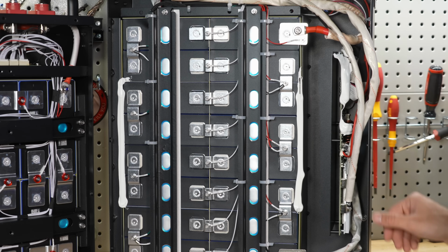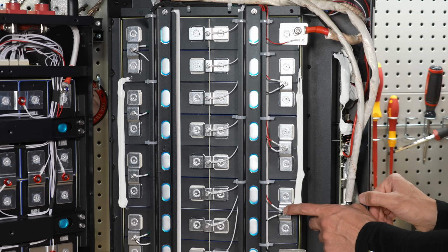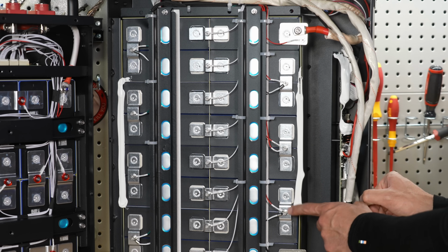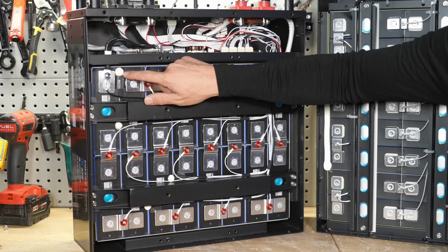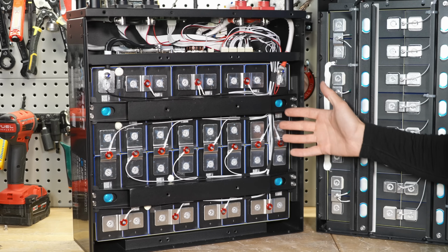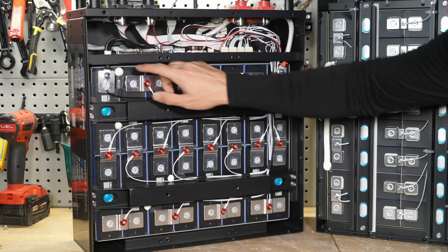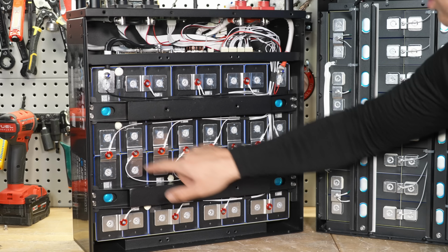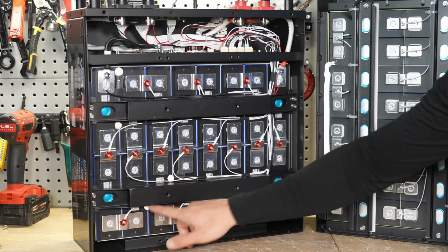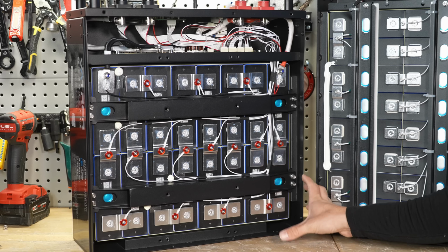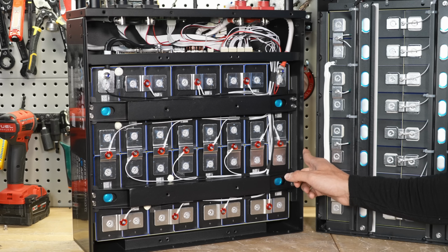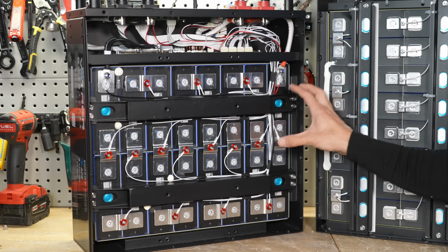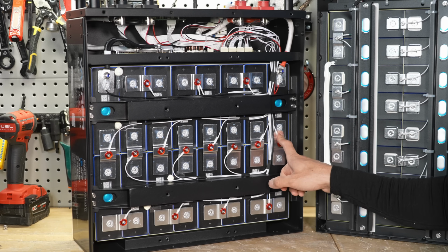Next, the Ecoworthy has potted ring terminals for the temperature sensors. On the Vatrer, they're only glued in place, and they're unevenly distributed. Check this out - we have 1 sensor here, 2, 3, and 4, but there's no sensors on this side. So if this side gets cold and you try to charge it, the BMS will not know, and that can cause permanent damage.